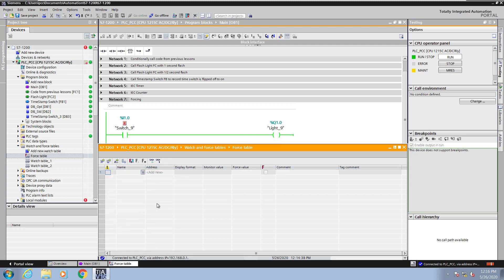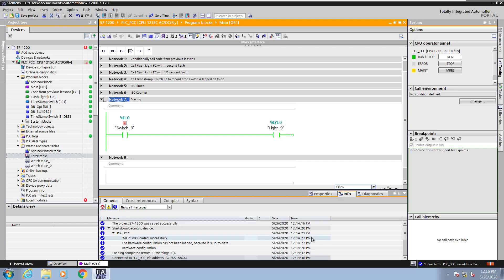Now I will delete the force entry and the value is still being forced in the PLC because the force job resides inside the PLC.